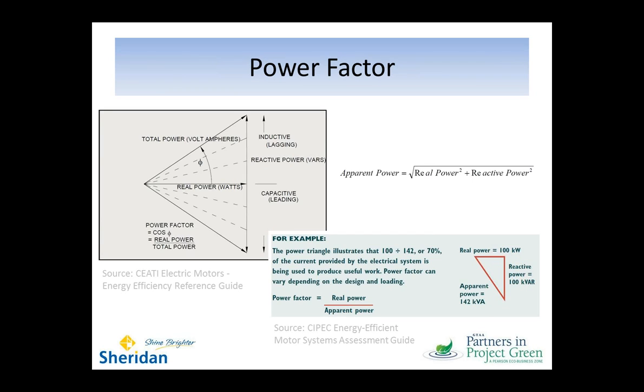I've included a background slide or two just to review some of the concepts that come up when we're discussing motor issues. And the first one that always comes up is the idea of power factor. An induction motor, like we see in most facilities, will require both real and reactive power. The real power is the stuff that we measure with our energy meters. It's the stuff that creates work and heat. It spins the motor, it lights lights. The reactive power is what we use to establish stored energy fields, like magnetic fields that we need in order to get the motors to function as they're supposed to.